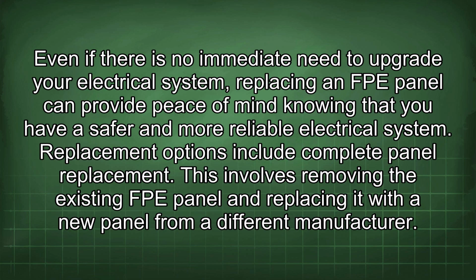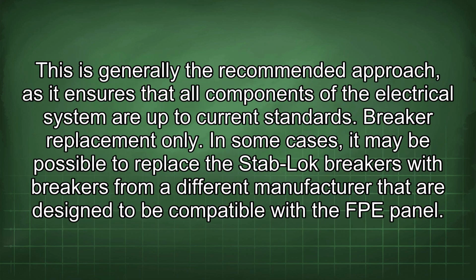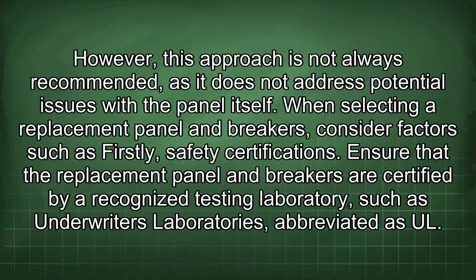Replacement options include complete panel replacement. This involves removing the existing FPE panel and replacing it with a new panel from a different manufacturer. This is generally the recommended approach, as it ensures that all components of the electrical system are up to current standards. Breaker replacement only. In some cases, it may be possible to replace the Stab-Lok breakers with breakers from a different manufacturer that are designed to be compatible with the FPE panel. However, this approach is not always recommended, as it does not address potential issues with the panel itself.